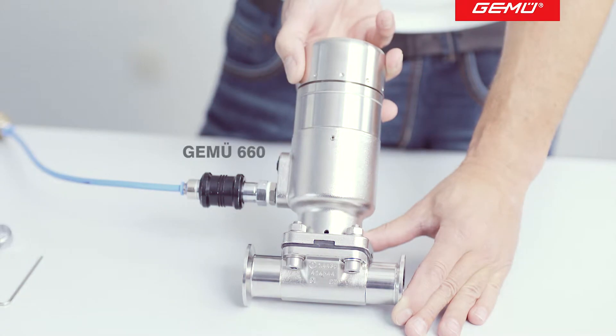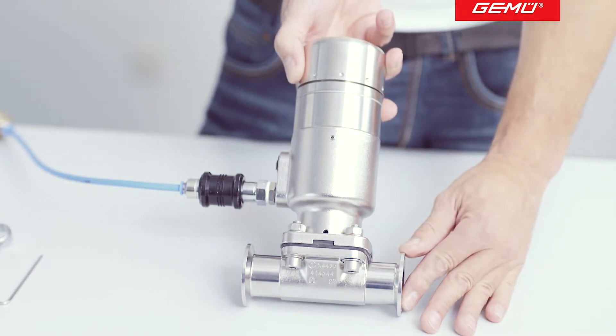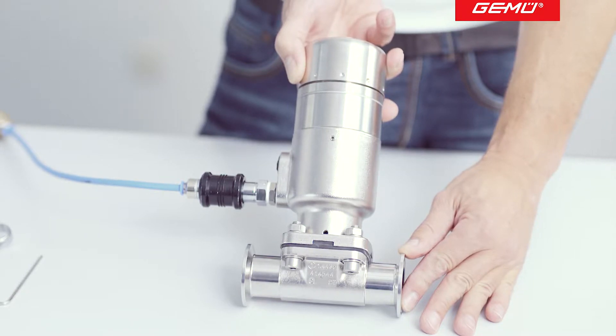A valve for filling processes is mostly exposed to very high switching cycles. The wearing parts, above all the diaphragm, are subjected to extreme mechanical loads. The GEMÜ 660 diaphragm valve has been specifically designed for fast and high pulse frequencies and therefore has a closing limiter and opening limiter as standard.